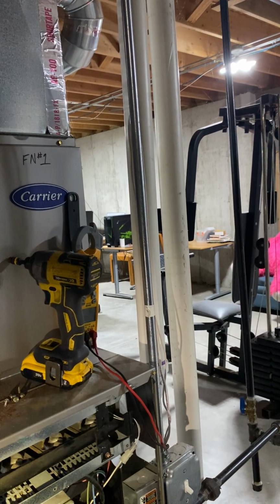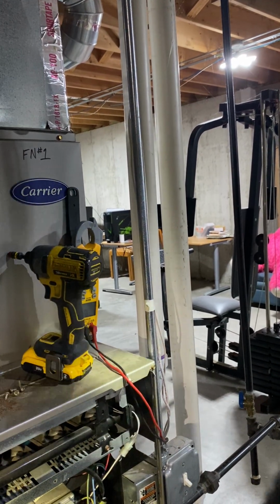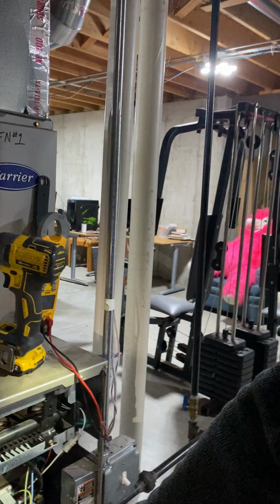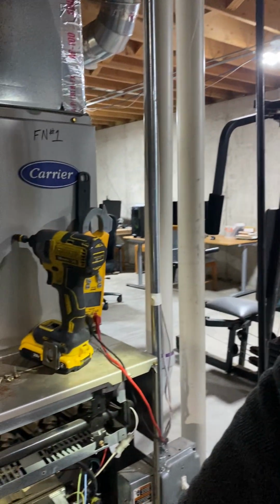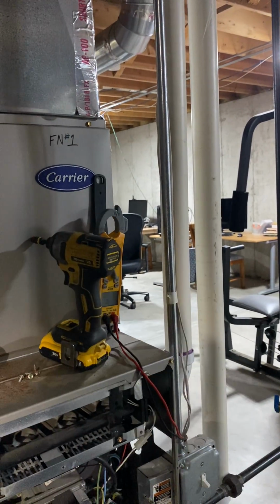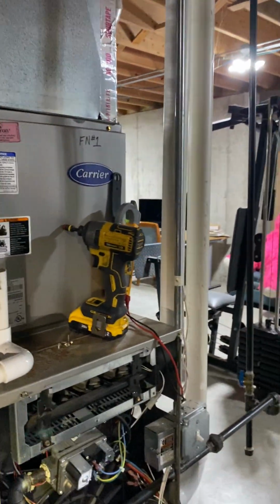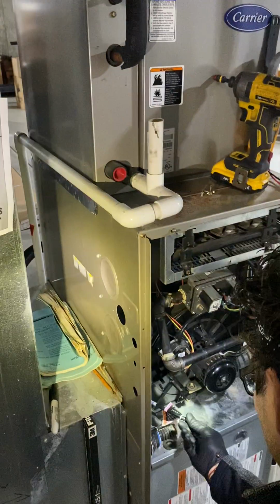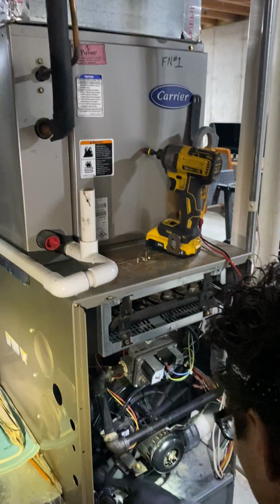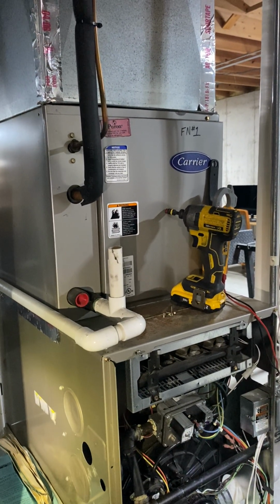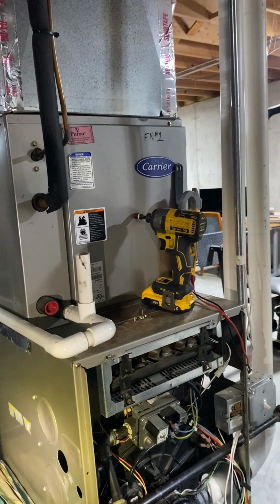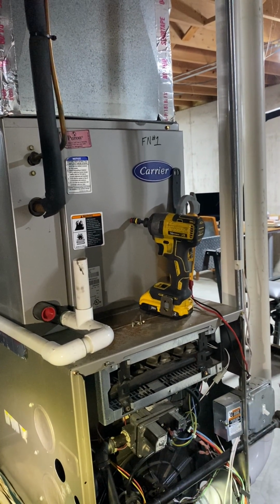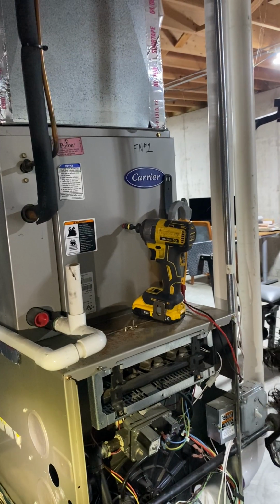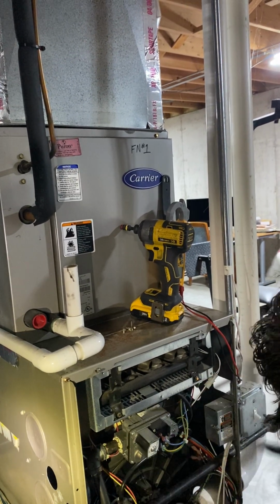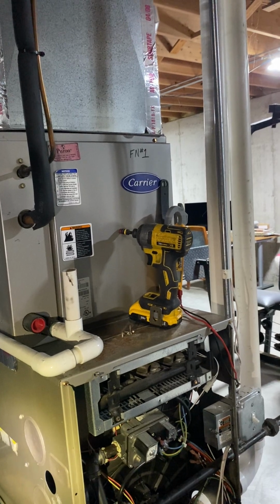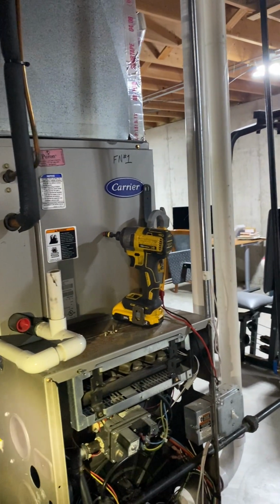And that includes all the other testing. What I'm going to do is we're going to have to remove that white looking trap, clean it out, get the water out that's in the system, because where the other end of the tube is, there's water inside of there still. There's not supposed to be water, it's supposed to be air. So when this turns on, it creates a draft. That air is pulled in through the tube and it pulls in this pressure switch to continue on with the next part of the heating cycle. But because there's water in the system, it's not doing what it's supposed to do.